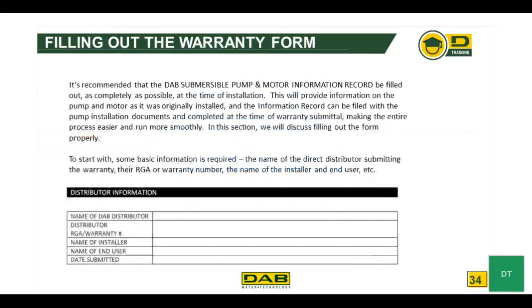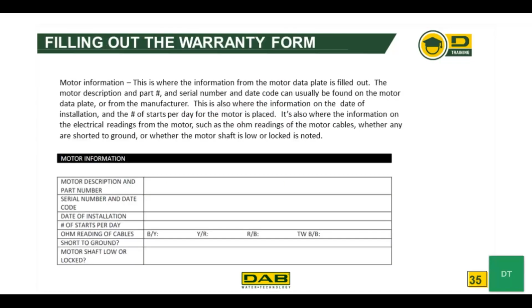In this section, we're going to talk about filling out the form properly. To start with, some basic information is required. In this section, we're going to talk about filling out the motor information. This is where the information from the motor data plate is filled out. Again, this is usually easier to do before the motor is installed. The motor description and part number, the serial number, and the date code can usually be found on the motor data plate or from the manufacturer.